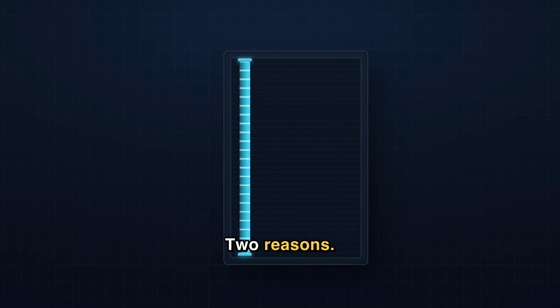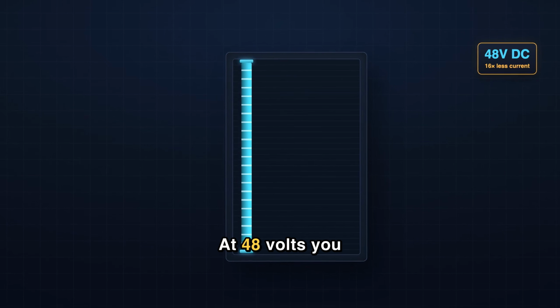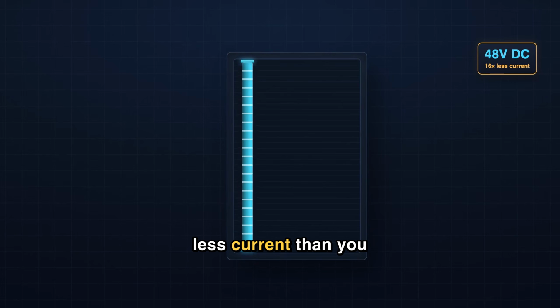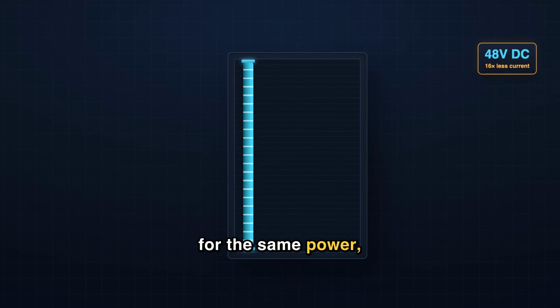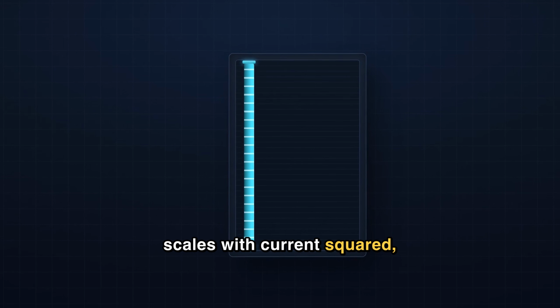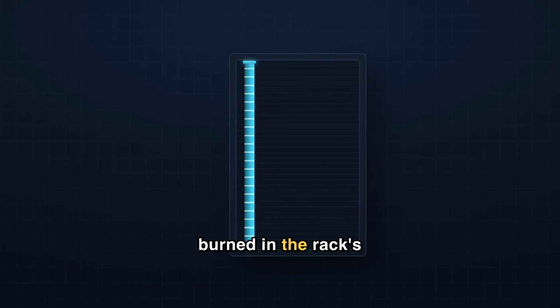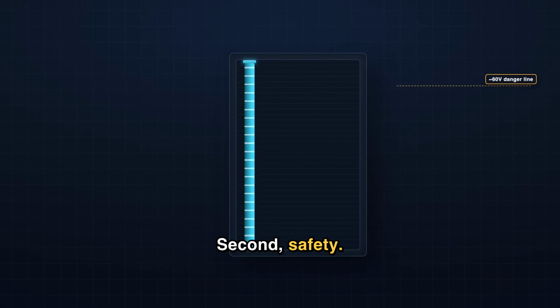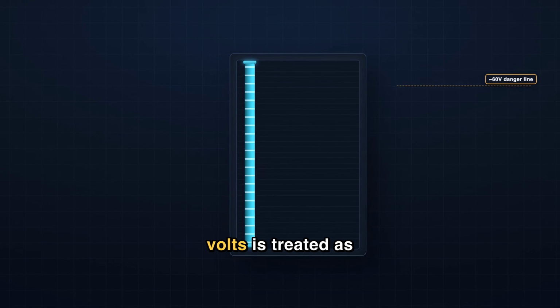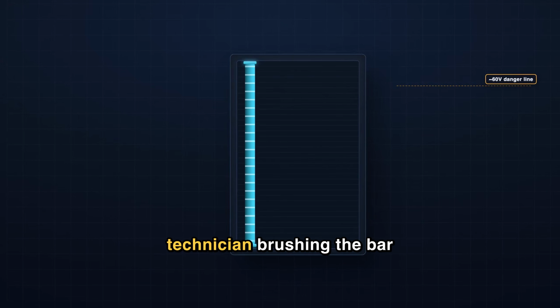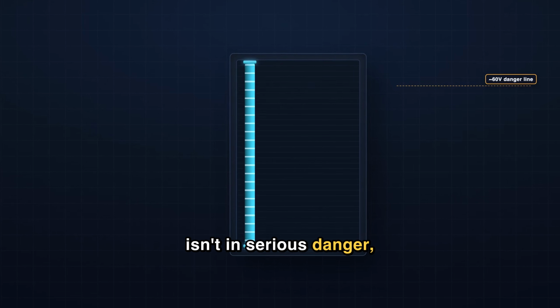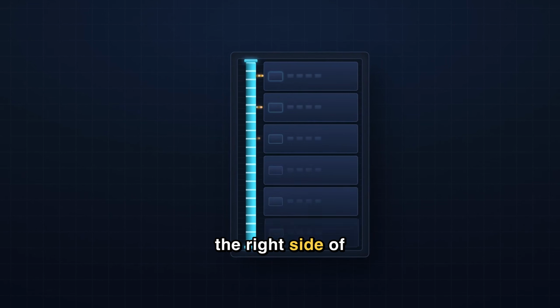2 reasons. First, current again. At 48 volts you push about 16 times less current than you would at 3 volts for the same power. And since wasted heat scales with current squared, that slashes the loss burned in the rack's own wiring. Second, safety. Anything under about 60 volts is treated as low enough that a technician brushing the bar isn't in serious danger. So 48 stays on the right side of that line.